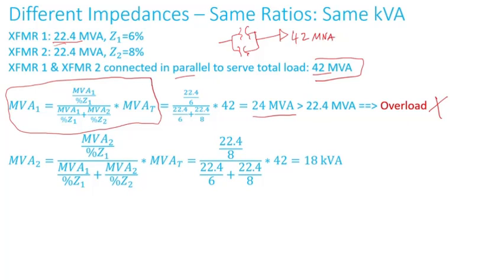If I do the same thing for transformer two, transformer two will carry 18 MVA. So 18 MVA is less than 22.4 MVA, meaning transformer two is within its rating.